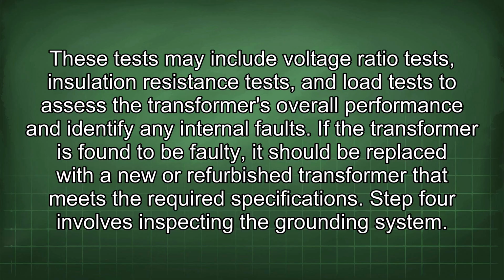These tests may include voltage ratio tests, insulation resistance tests, and load tests to assess the transformer's overall performance and identify any internal faults. If the transformer is found to be faulty, it should be replaced with a new or refurbished transformer that meets the required specifications.